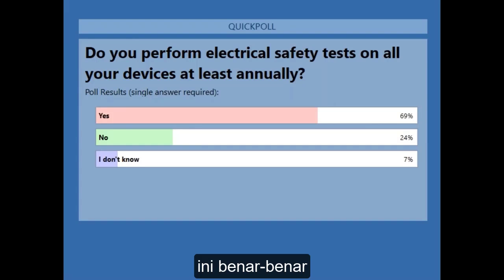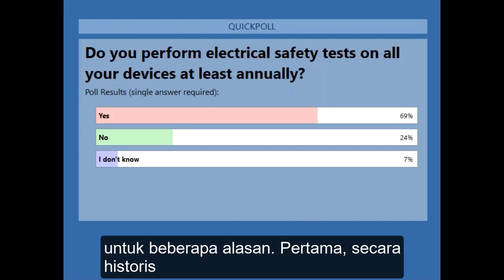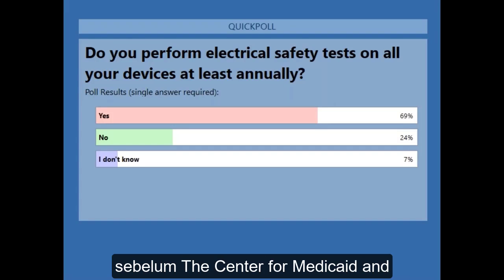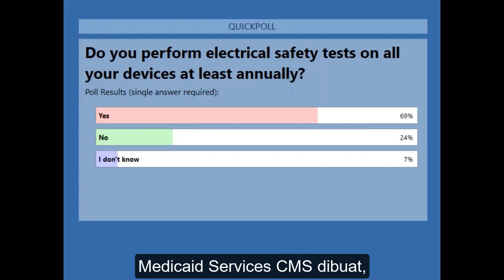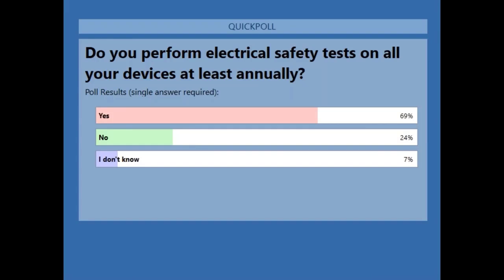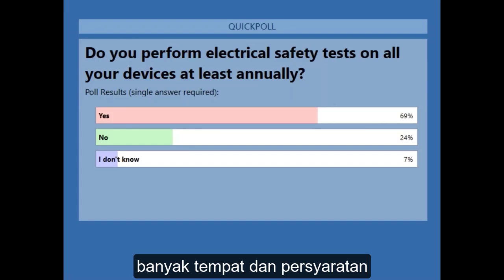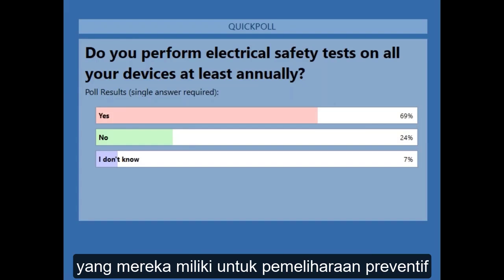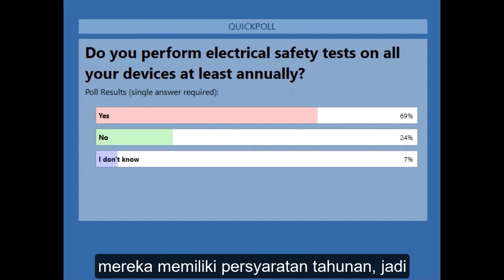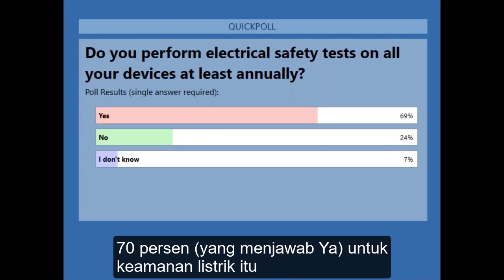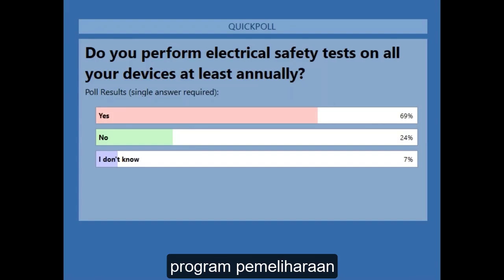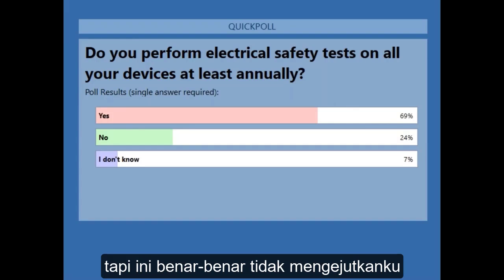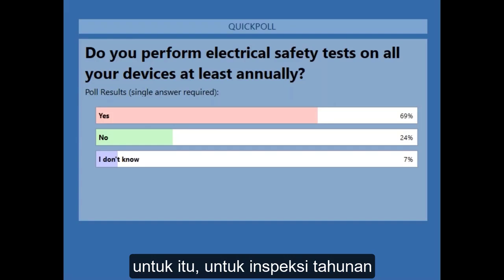This is Ben. This is really not surprising to me for a couple of reasons. First, historically, before the Centers for Medicare and Medicaid Services, CMS, came out, a lot of places had a 100% on-time completion requirement. For preventive maintenance, they had the annual requirement. So an almost 70% result for that electrical safety doesn't surprise me. And then later on, we'll talk about the alternative equipment maintenance program. But this really does not surprise me for the annual inspection, to make sure that's happening.